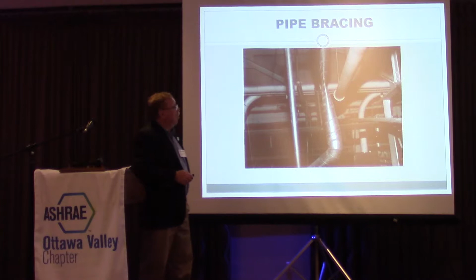One, most pipes don't need to be braced - let them just swing all over the place. Now, the Code of the United States says if I have a pipe that's less than 12 inches from the ceiling, and that movement is not going to impinge on anything else, we're going to let that swing, as long as the connection at the top can handle taking moments - in other words, it's got to have some kind of swivel system. So what happens here is none of these are braced, and this thing, swinging back and forth, just crushed the hell out of this duct. All these pipes were probably swinging all over the place.